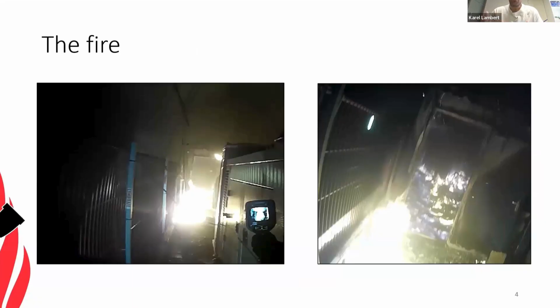After knocking down the fire, we started boundary cooling. You don't only need water to extinguish the fire, you also need water to cool the concrete structure, because if the heat release and temperature go up, you get spalling and might have problems with structural stability. The rule we have is 1/3 of the water is used to extinguish, while 2/3 is used to cool the structure of the tunnel.